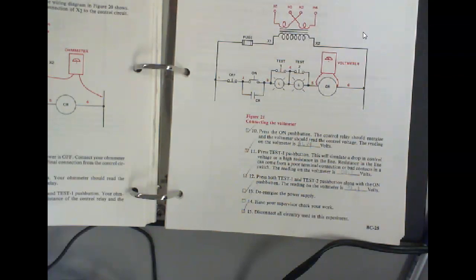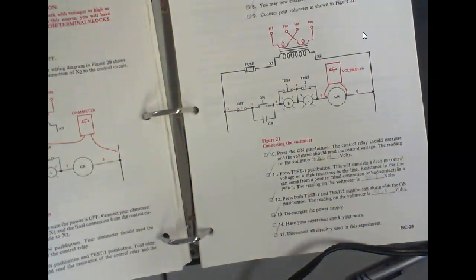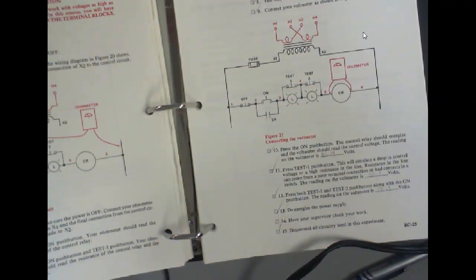And what we're trying to see is what basically, so relays have what we call a pull-in voltage. So they generate enough current to generate the magnetic field. And then it has what we call a holding current or a holding voltage. So that's how much it takes to keep the magnet pulled in once it's connected.